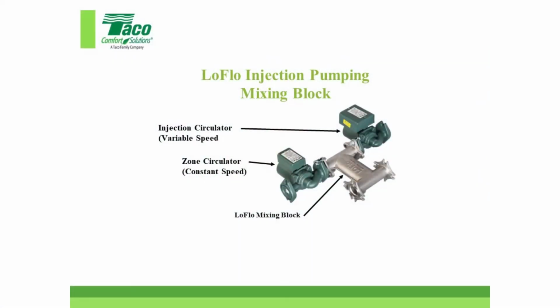Here's a picture of the low flow injection pumping mixing block. Okay, so actually if you go down to our booth, you'll see some. These are actually made at our foundry in Vietnam. We have a stainless steel foundry in Vietnam. So the zone circulator is constant speed, right? This is a TACO circulator, very reliable, very quiet. Constant speed, gets out to the chill beams. And the thermostat and the humidity sensor control this, and we have a thermometer on this pipe. As that warms up, this pulls off some cold water to bring it back in.